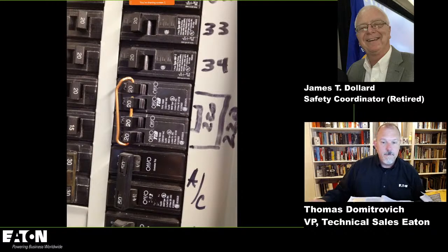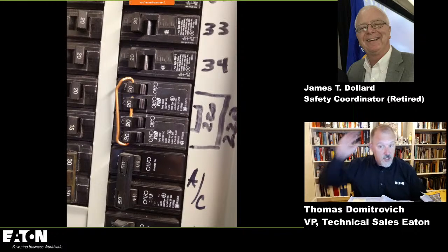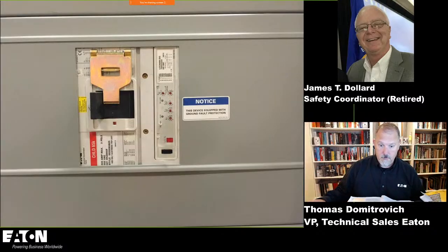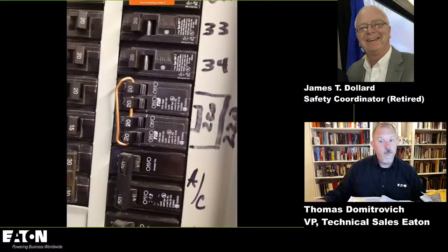But it's important to understand, you've got to use the identified parts for handle ties, etc. And like you talked about the shared neutral application, where you want to make sure that you disconnect everything. When you turn it into the off position, it doesn't have to trip to the off position, but you want to make sure you disconnect all of those conductors. Yeah, and I don't believe that there's a manufacturer out there that has an identified handle tie for split circuit breakers. So, no, everything's wrong there.